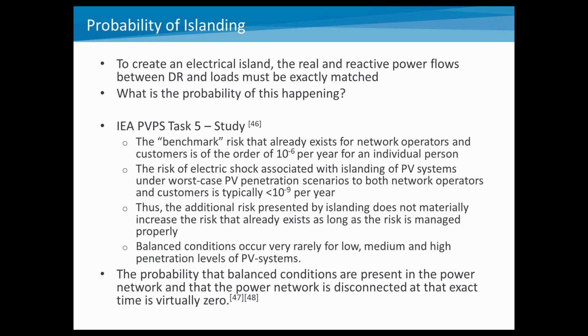So if all of a sudden you have a lot of load and a small distributed generation, that distributed generation isn't going to be able to maintain an island. When you separate into an unintentional island system, if you have a small amount of distributed generation, you most likely won't be able to maintain an island condition. And if you have an overabundance of distributed generation, again, it'll be difficult to maintain that island without moving outside the voltage and frequency nominal set points.